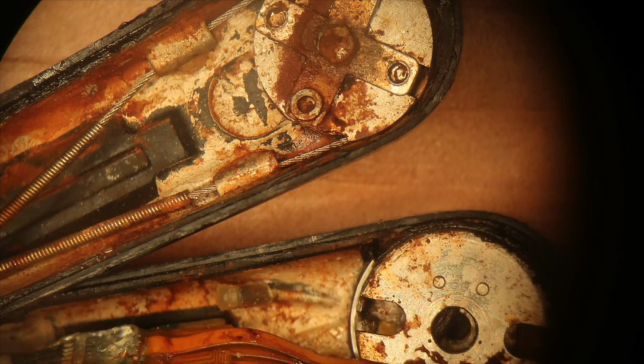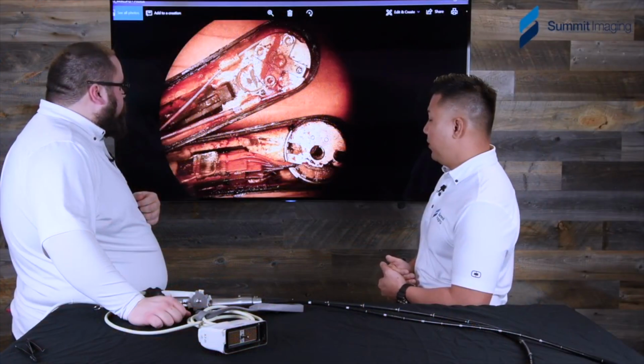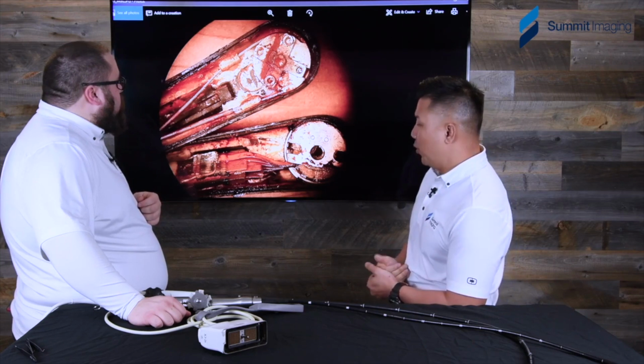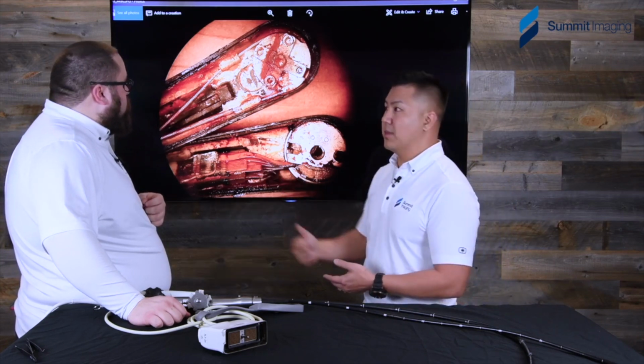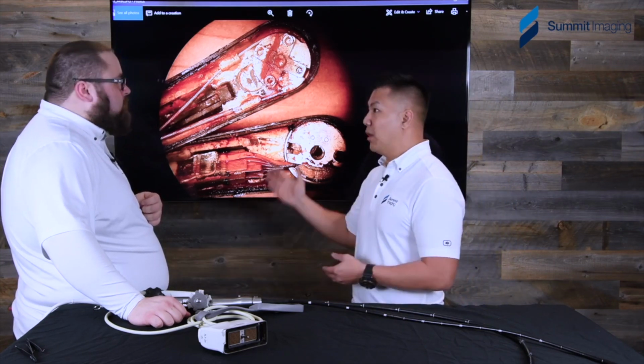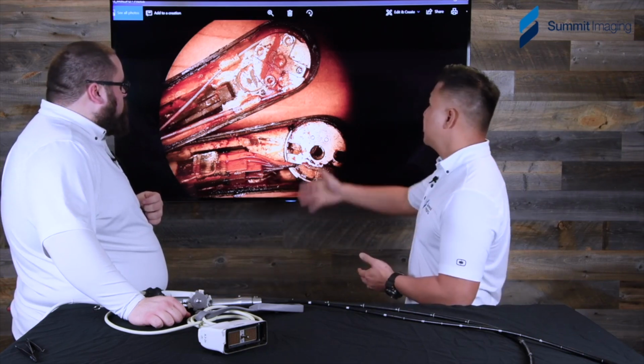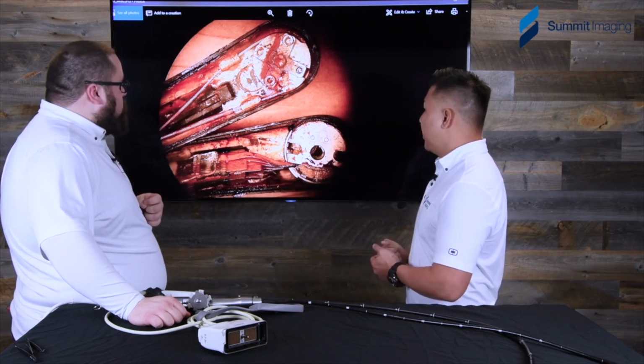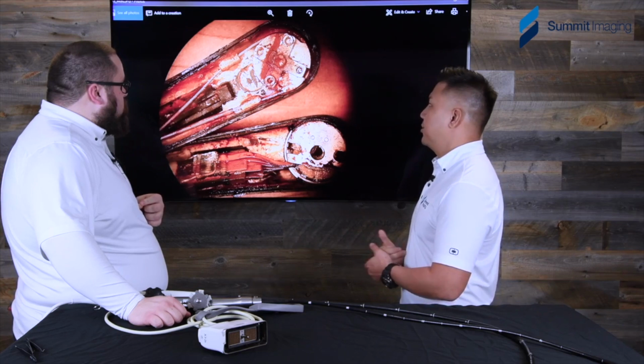You've got to be careful to make sure the rust doesn't get onto the surface of the crystal, which is going to cause refraction with the image and it won't look right. You want to make sure that there's no leftover rust, because it will rust more if you don't get it all out the first time. And so these are the kinds of things that we're seeing. But again, pretty severe fluid intrusion here.